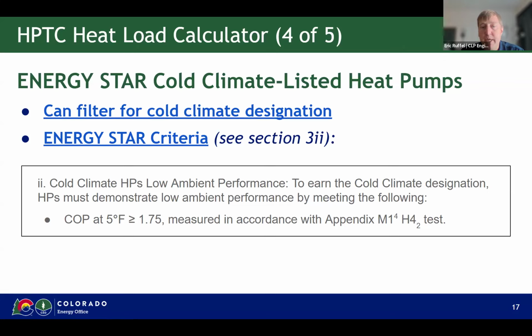Although some manufacturers will have a chart showing COP by temperature, since there is variation by manufacturer, another option to consider is the Energy Star cold climate listed heat pumps. To meet the Energy Star criteria, your COP at 5 degrees has to be greater than 1.75. Since 5 degrees is below the temperature for each location in the tool, if a heat pump is cold climate listed under Energy Star, it meets the criteria for any location in Colorado in that tool. That's another way to simplify the documentation process.